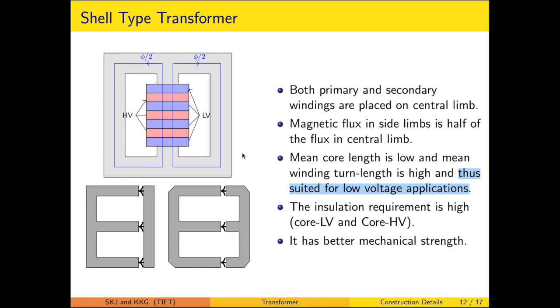So this suggests that the shell type has a lower mean core length, where the mean winding turn length is high. Therefore, it is suited for low voltage application. Because the windings are to be wound on the central limb, which is the thicker one, the mean winding turn length is higher. As mentioned, when the interleaved structure is there, it requires a higher amount of insulation. However, it provides better mechanical support because the windings are placed on the central limb.